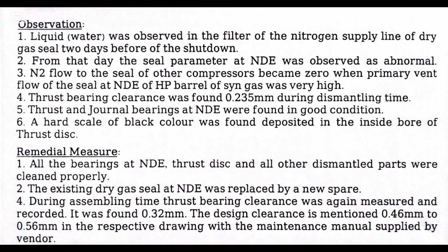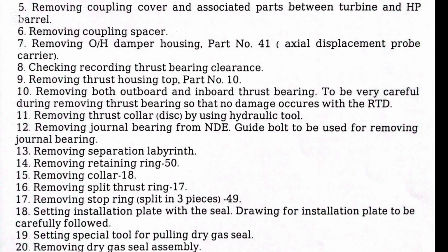Also, thrust bearing clearance was found to be 0.235 mm during dismantling time. Thrust and journal bearings at the non-drive end were found in good condition, and also a hard scale of black color was found deposited in the inside bore of the thrust discs. To overcome this problem, necessary action was taken immediately. In our warehouse there was a dry gas seal, and the dry gas seal needs to be changed with a new one.